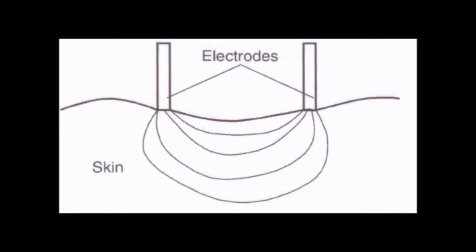In the bipolar configuration, the RF energy is generated using two electrodes. The thermal and clinical effects can safely and comfortably be sent and received from electrode to electrode at the treatment site. Bipolar energy is more localized and controlled, making it more safe and more comfortable for the patient. It has a more reliable depth of penetration and requires less energy to achieve the same heating effect than monopolar RF. In summary, the main difference between monopolar and bipolar configuration is the way in which the current is controlled and directed to the body.